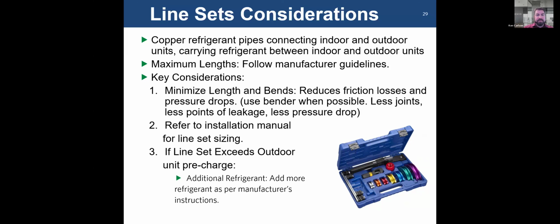It changes depending on the size of the units. Dealing with multi-zone mini splits, your line set size is dictated by the interior unit that it's going to. So it will change. You could, on a multi-zone system, have 3 different size line sets. It's not uncommon. If your line sets exceed the outdoor unit charge, you will need to add refrigerant. In the manufacturer's posted installation manual, they typically will tell you how much refrigerant needs to be added. When you're dealing with mini splits, they don't want you using subcooling or superheat, which we'll talk about shortly. They want you to weigh it in. All right. So, they'll typically come, and we'll talk about this in a little bit.